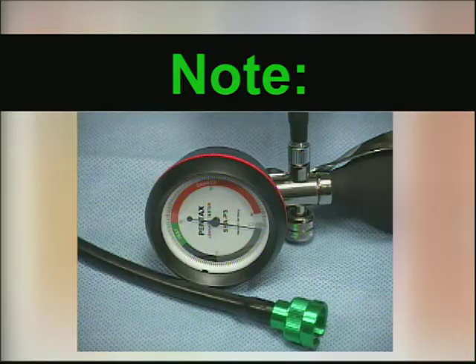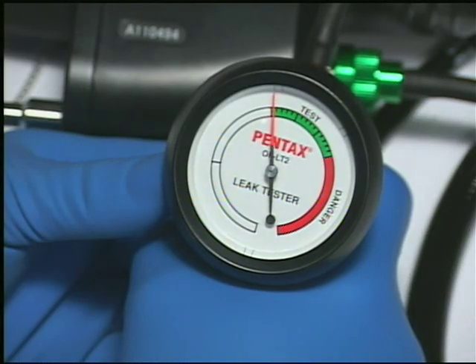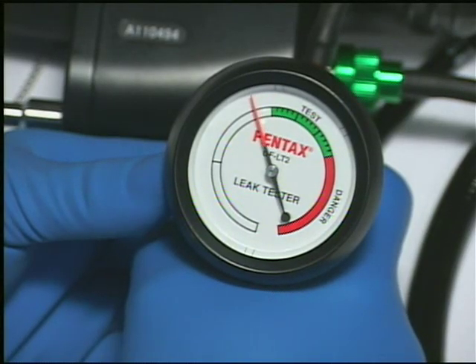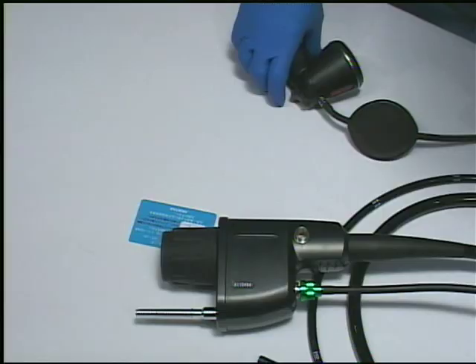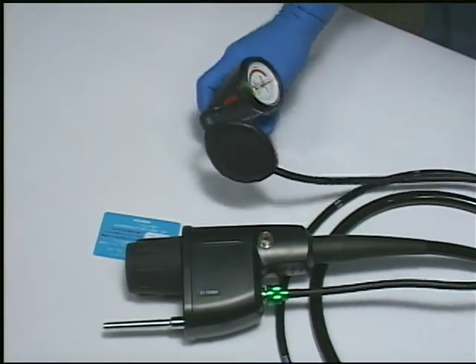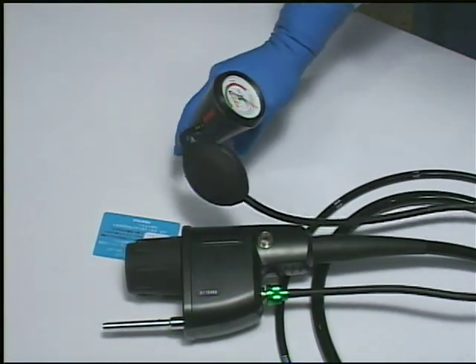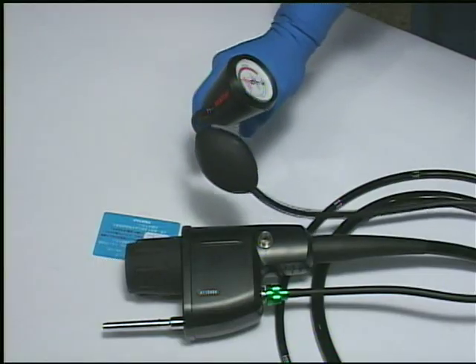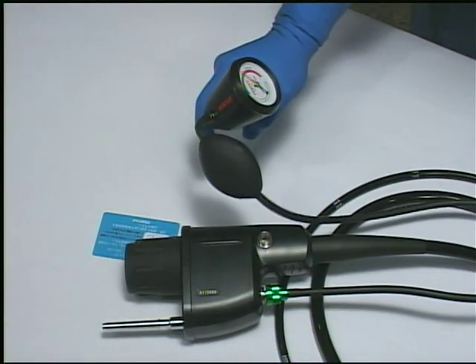Note: be certain that the pressure release valve on the handle of the leakage tester has been tightened. Do not immerse the endoscope if the gauge indicator does not remain in the green zone. Stage 2. Wet test. After determining the absence of any major leak in Stage 1 testing, Pentax endoscopes may be immersed to test for loss of integrity in their watertight construction.